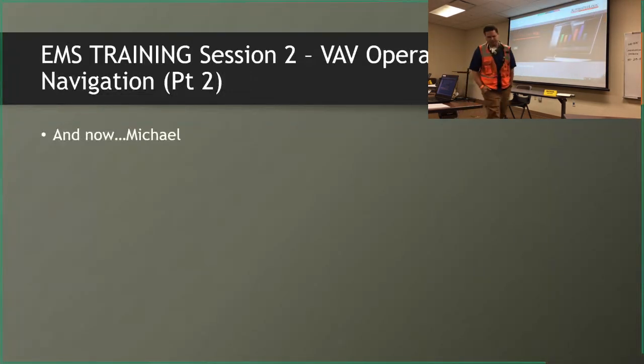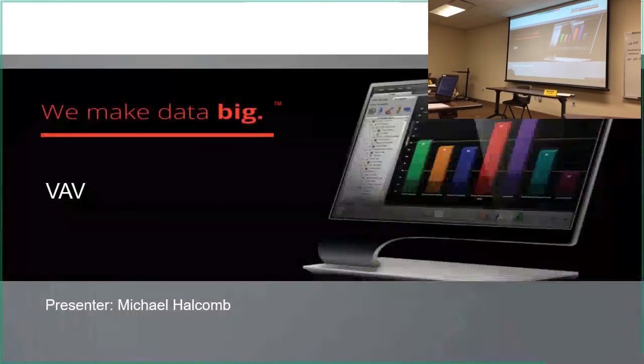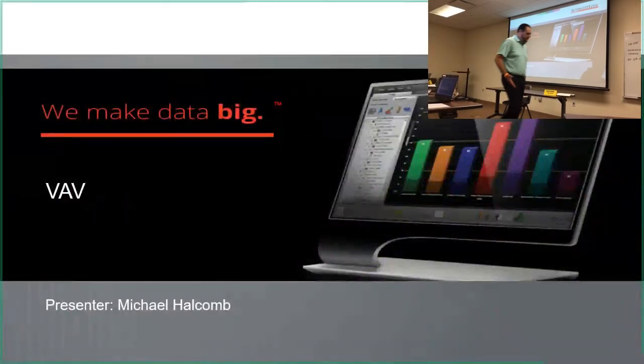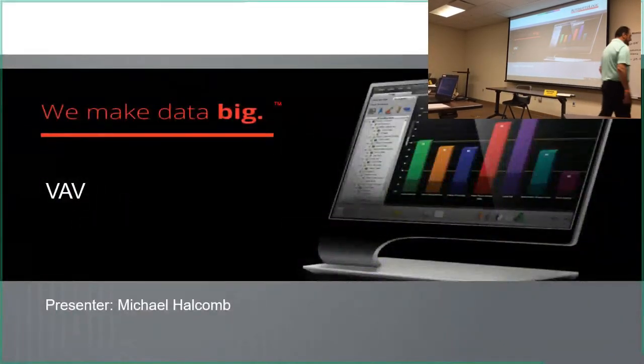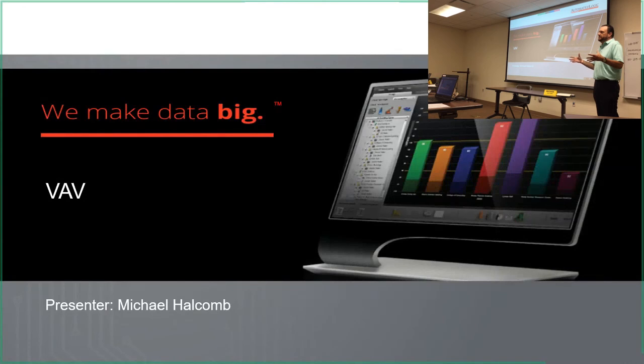Okay. And we'll swap. So VAV box, when I hire a new employee or when we hire a new controls guy, test and balance guy, it's the most populated piece of equipment that you have in each building, in every building. I mean, every time we do a hospital, big building, all these large facilities, VAVs are number one, the most common equipment in the building.